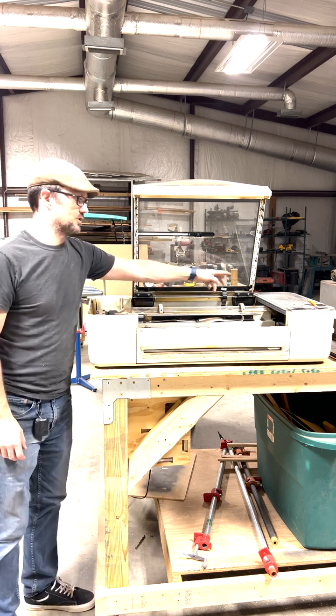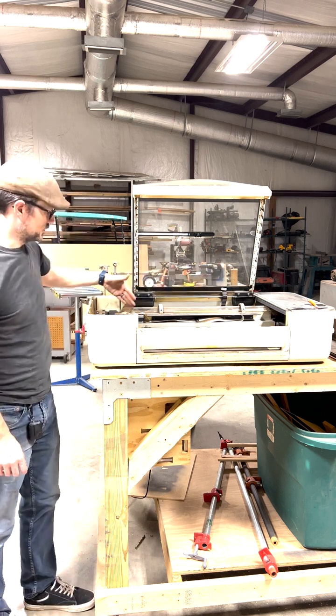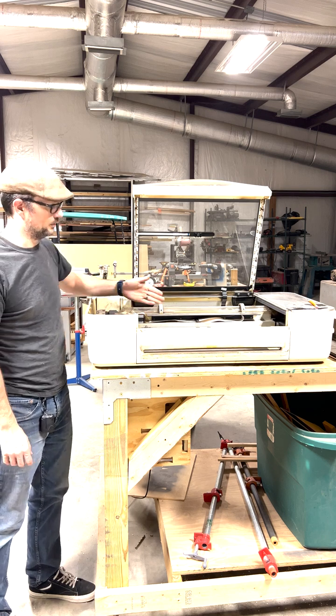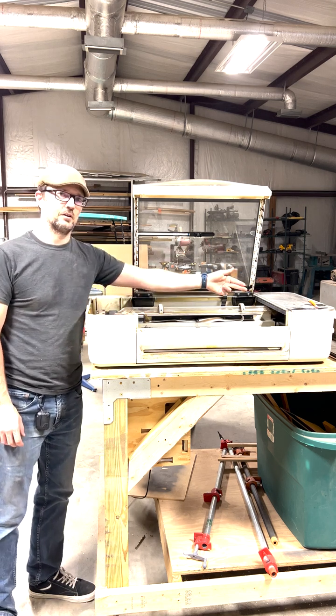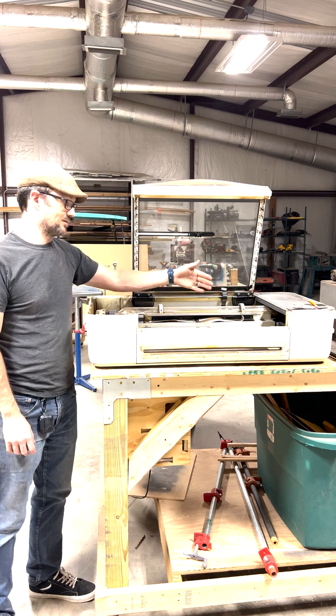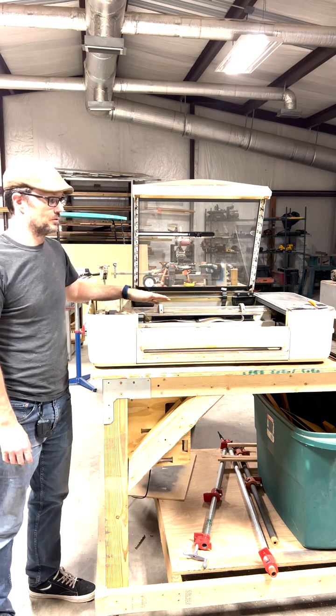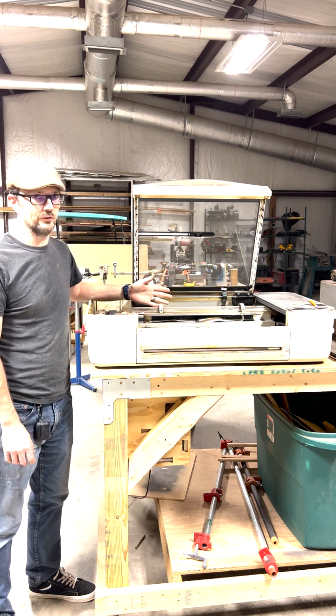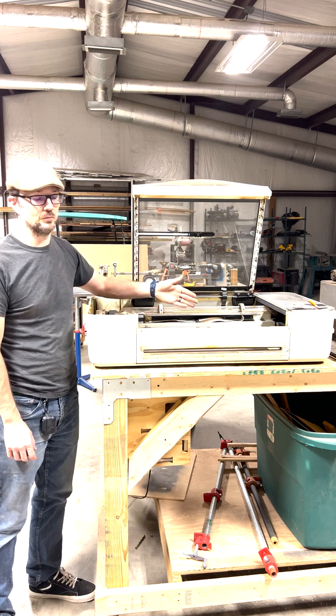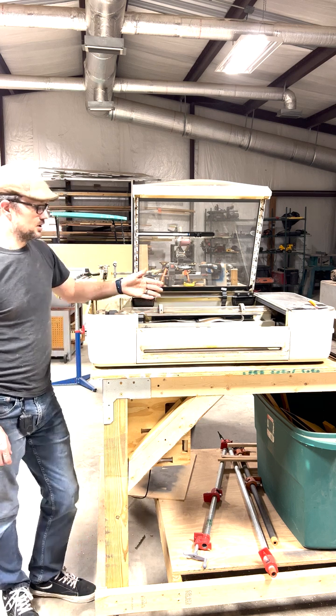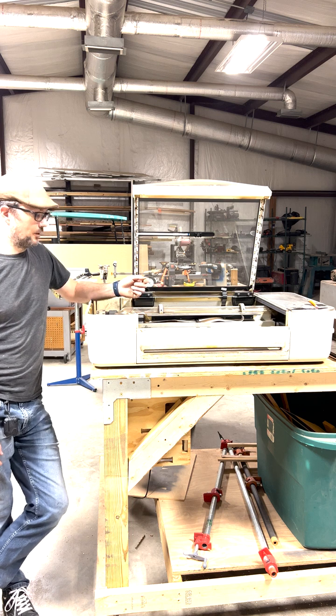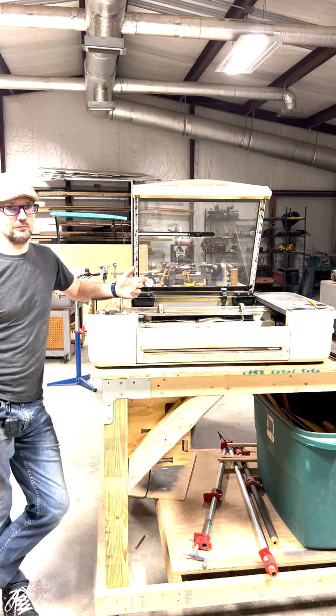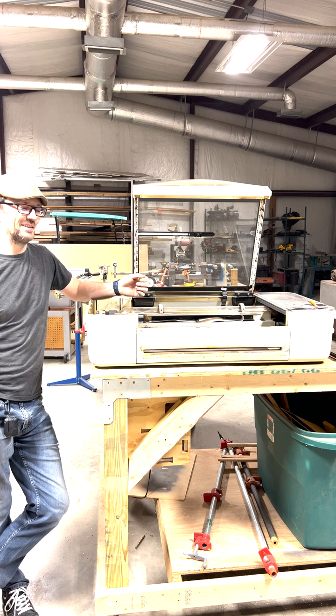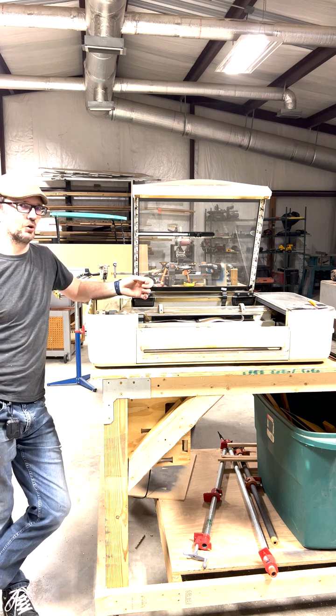So there's a red wire that's built into the power supply that runs under the machine, back through the chain guide, under the tube, and then connects to the far side. Now that is high voltage shooting through that. It's 30,000 volts of DC, and that's what powers up the tube and creates the laser beam. So the wire that they use is rated for 40 kilovolts, just 40,000 DC. But the insulation is very flimsy and not great.